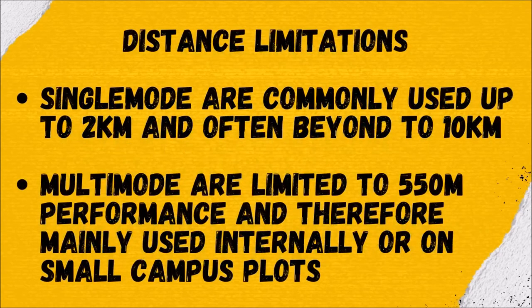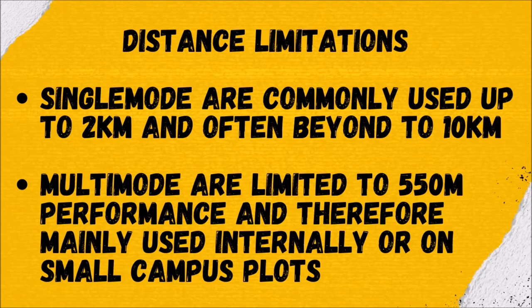Distance limitations: single mode are commonly used up to 2 kilometers and often beyond to 10 kilometers. Multimode are limited to 550 meters performance and therefore mainly used internally or on small campus plots.